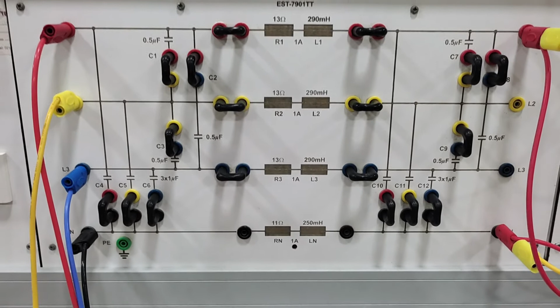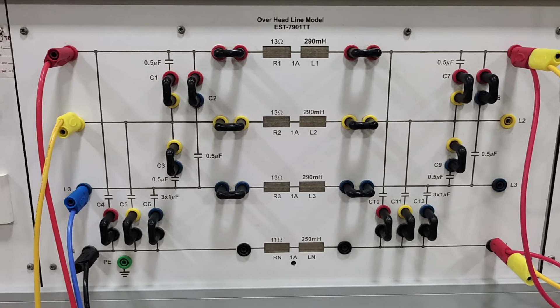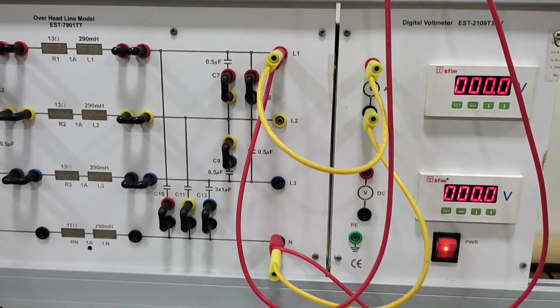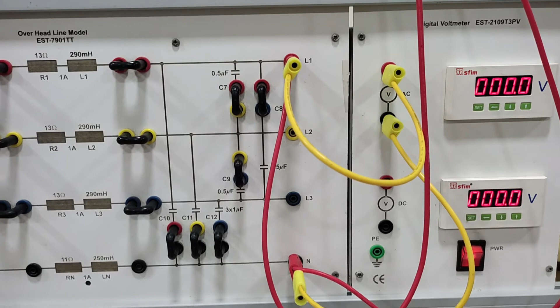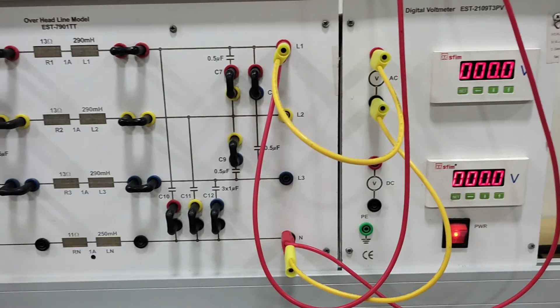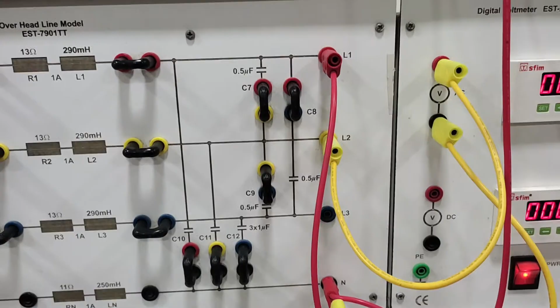From the transmission line, students, here you can see we have inserted the bridge plugs so that line to line capacitance gets connected. So we have inserted all the bridge plugs, and now here is the output of our transformer. Now what we have to do, we have to connect the first phase, that is this L1 phase, towards our neutral, because we have to short circuit this first phase with our neutral. Now how we will connect it, you will see.